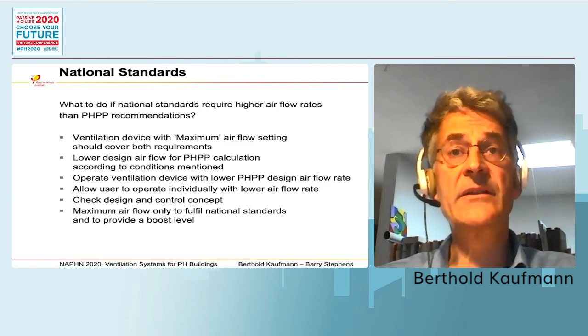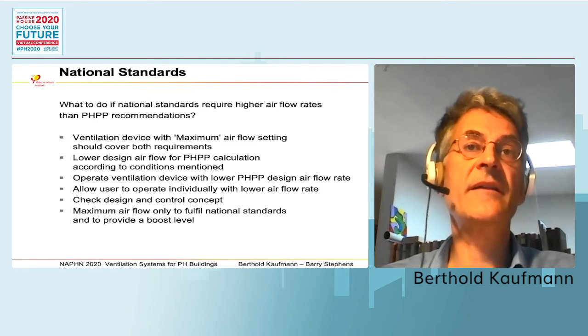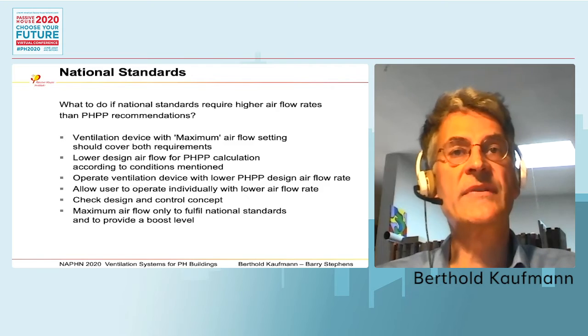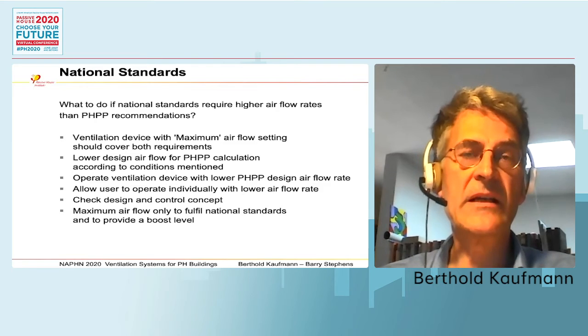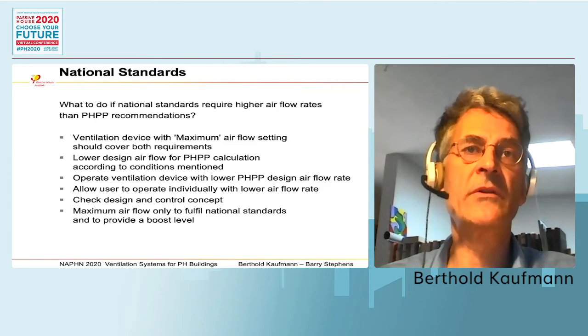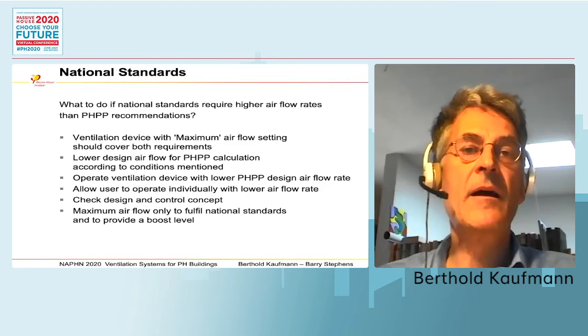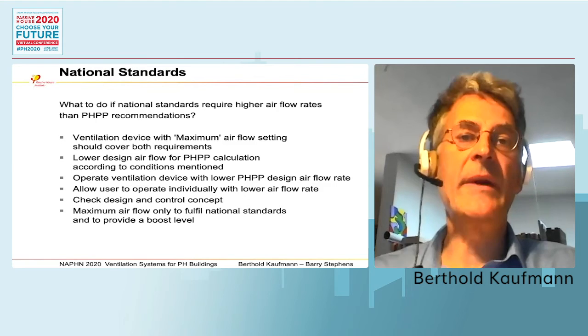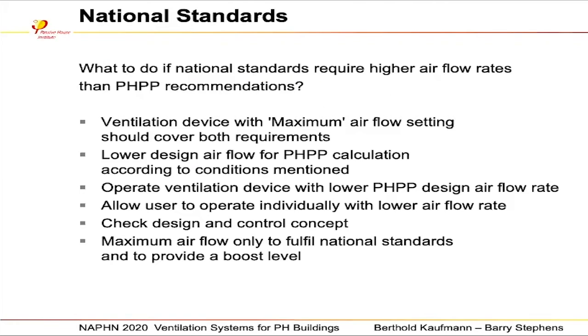So the idea is if your national standard asks for a higher airflow, you have to design your ventilation system to cover the maximum airflow setting. But you can recommend to the user later to have the system running with a lower airflow. This is a compromise which can work, but you have to decide and to discuss it with the client anyway.